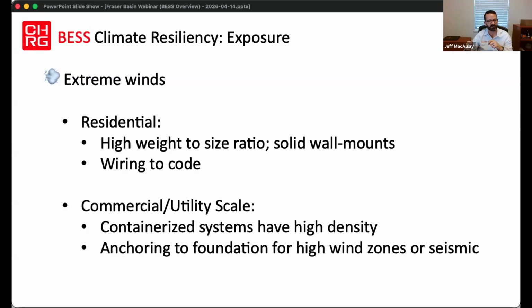If you're using flexible conduit, rigid conduit, or TECK cable coming out of these batteries going into the inverter, on an outside application, they're still going to make sure everything is fastened down and protected against extreme winds. So we don't really see a big trend on this, even in the US where there's tornadoes and hurricanes. This is typically not the issue. The structure itself is going to have much bigger issues if the battery is being ripped off the exterior wall.